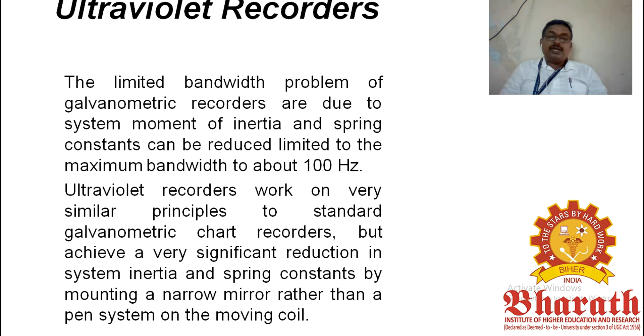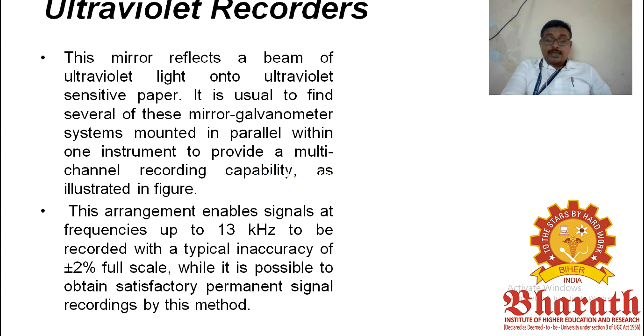So, in that criteria we follow ultraviolet recorders, which work on very similar principles to standard galvanometric chart recorders, but achieve a very significant reduction in system inertia and spring constants. A mirror reflects a beam of ultraviolet light onto ultraviolet sensitive paper. It is very simple. It is usual to find several of these mirror galvanometer systems mounted in parallel within one instrument to provide multi-channel recording capability. The arrangement enables signals at frequencies up to 13 kilohertz to be recorded satisfactorily. Special precautions are necessary to protect the ultraviolet sensitive paper from light before use and to spray a fixing lacquer on it after recording.